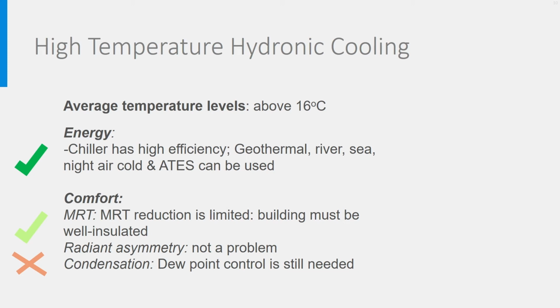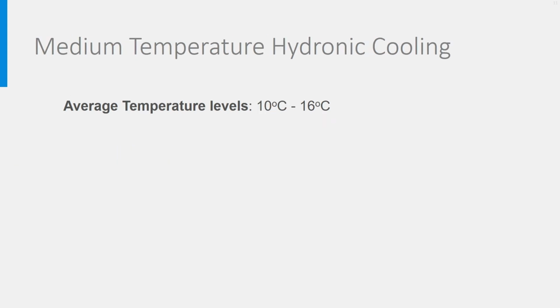Concerning comfort, the building must be well insulated, otherwise the cooling panels will not compensate enough for too high surface temperatures of the walls, a too high MRT therefore. And even with high temperature cooling, a good dew point control is needed in case of humid weather. Last but not least, many buildings have a system with an intermediate temperature somewhere between 10 and 16 degrees, and depending on their design, they will share advantages and disadvantages of the high and low temperature systems.